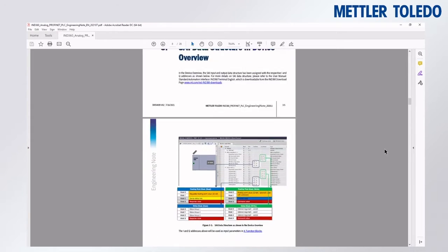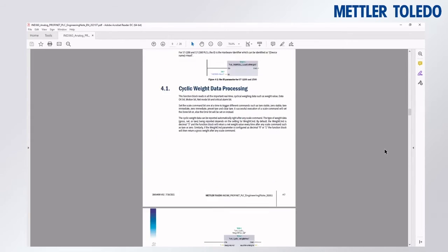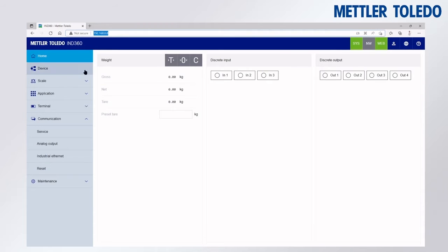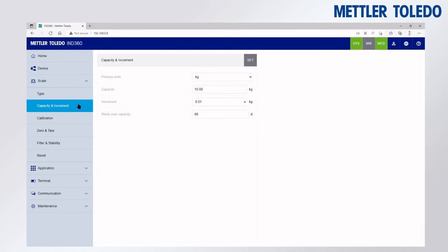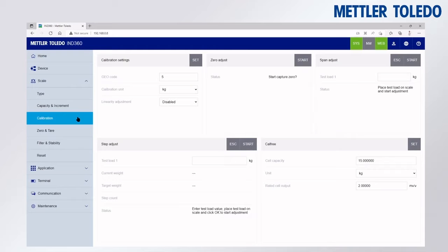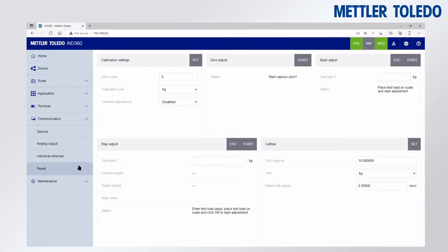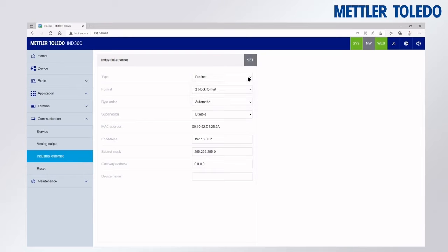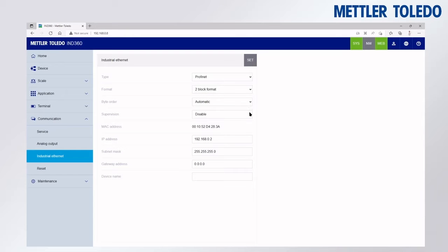The function block we'll be focusing on today is the weight processing block. First, we'll go to the web server of the IND360, where we can set many different parameters, but we'll focus on the industrial ethernet settings. We'll select PROFINET for this video. The block format can be 2 or 8 block, and supervision can be enabled or disabled to alert us if the PLC becomes disconnected.